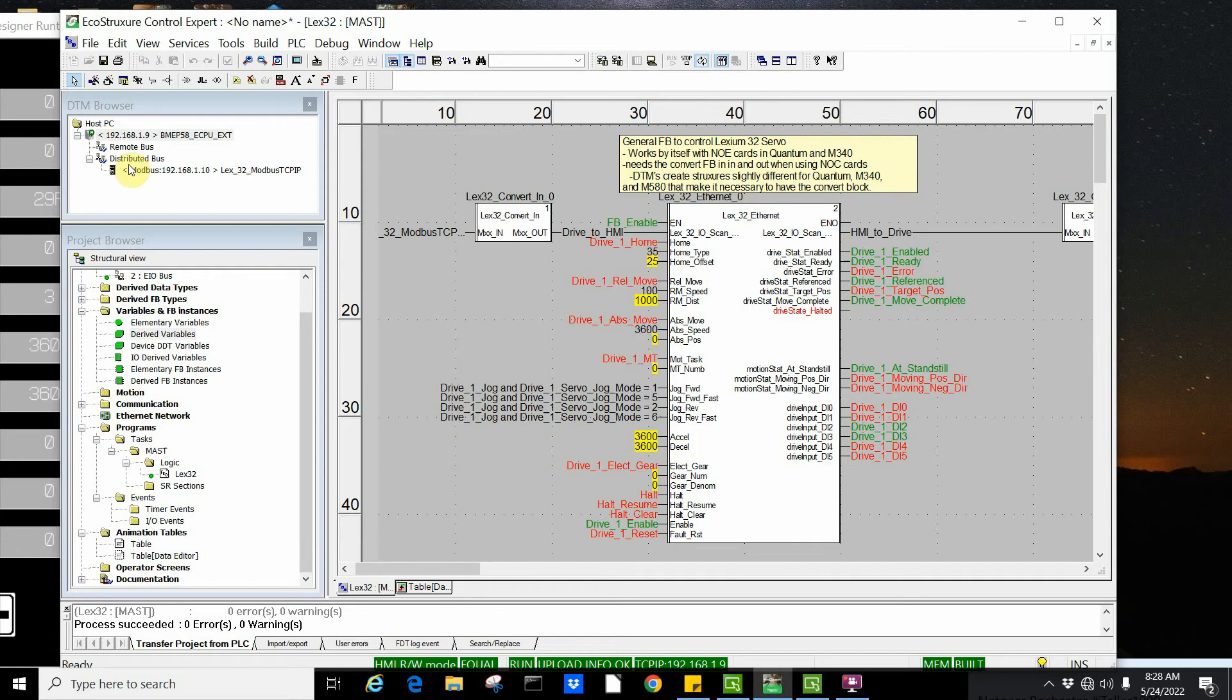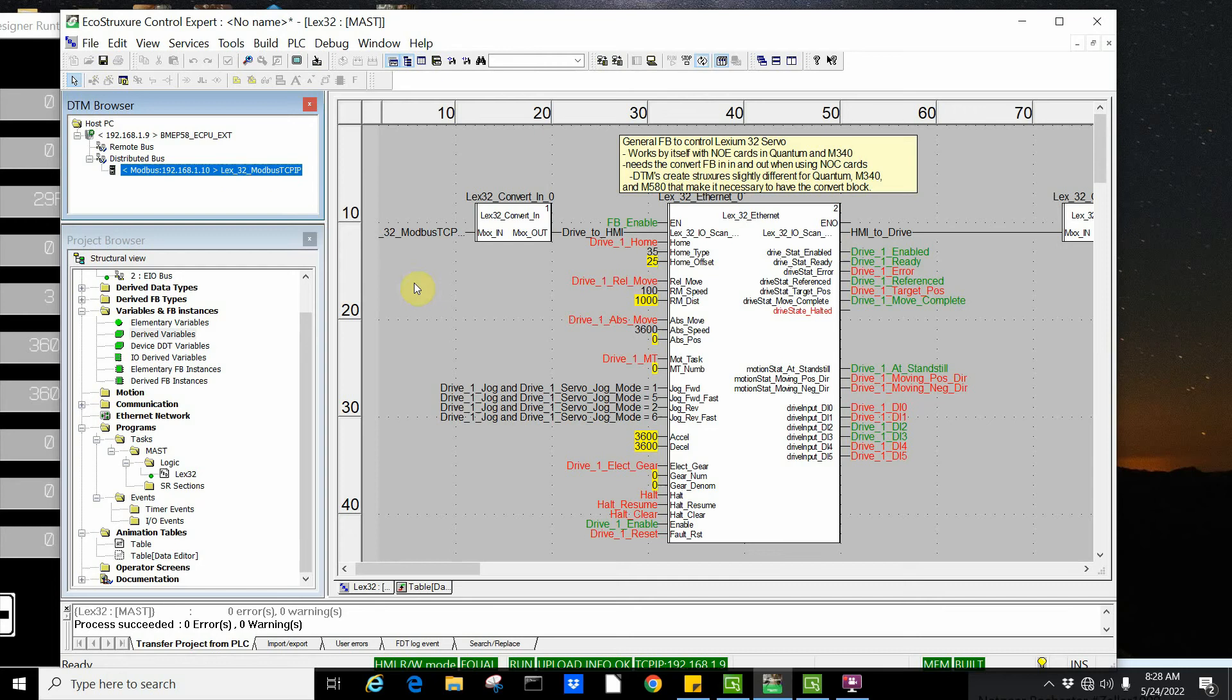We set up in the DTM browser a Lexium 32 drive using generic Modbus Ethernet. You could also use generic Ethernet IP. I prefer to use the generic DTMs because it makes it much easier to add duplicate drives and makes it easier to go from revisions.